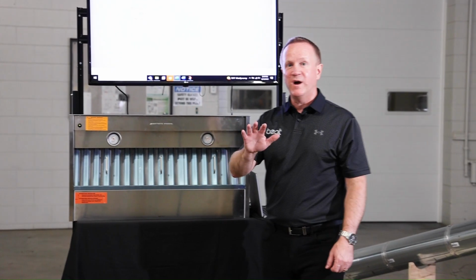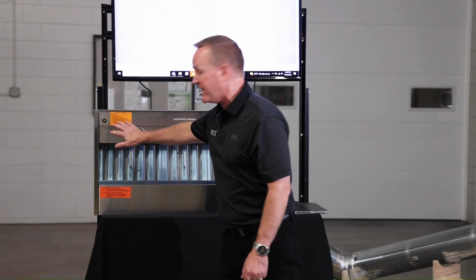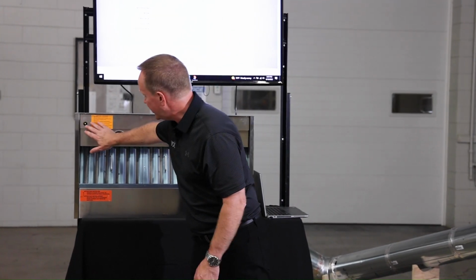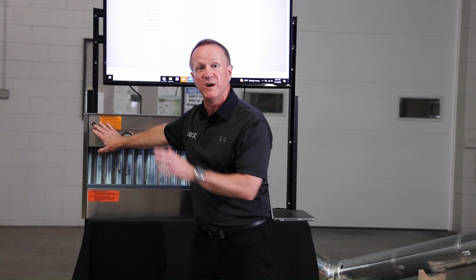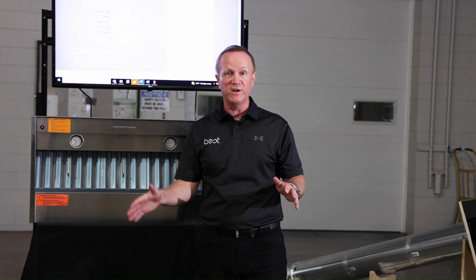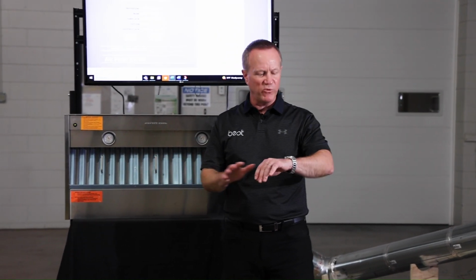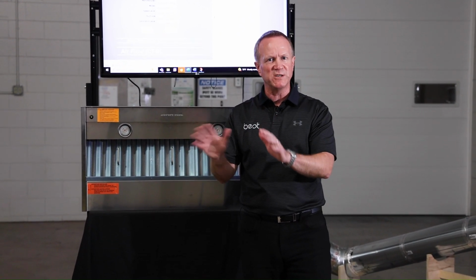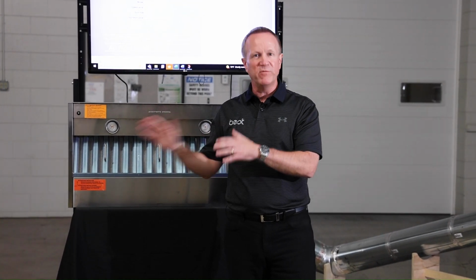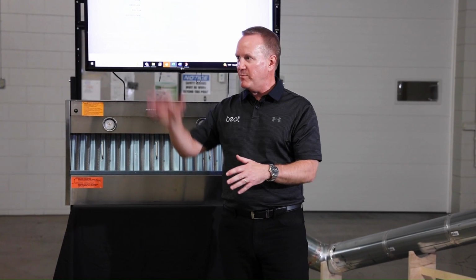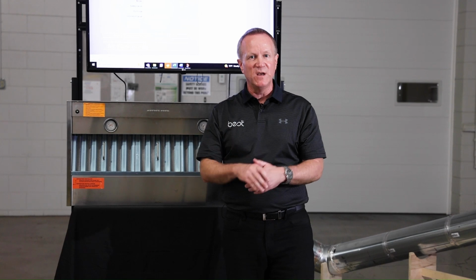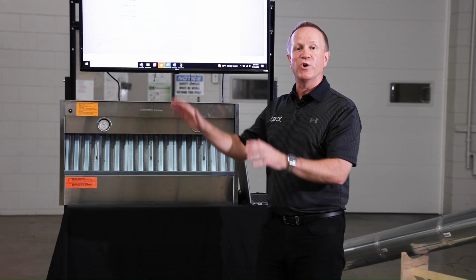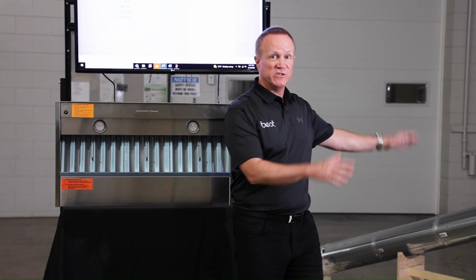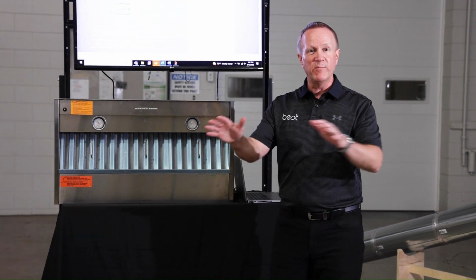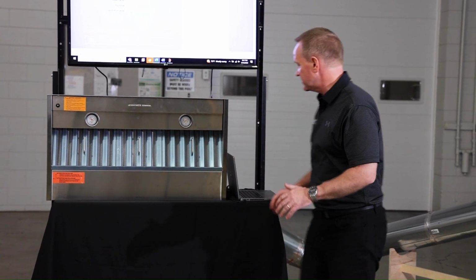Okay, so our installation and our calibration was successful, and I know that because my little green light is now solid and the hood has turned itself off. I believe we went through that 5-6 minutes approximately of calibration. We did hear it ramp up and down through various speeds. So what we're going to do now is we're going to take the airflow as installed, and we're going to do our measurements kind of in reverse.